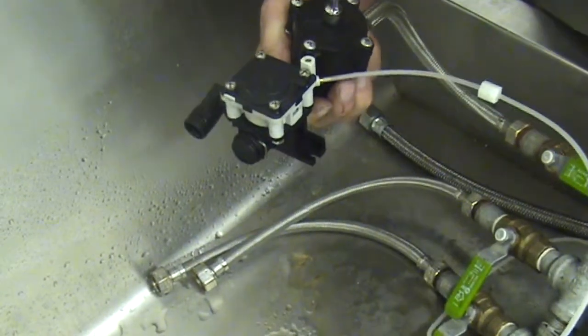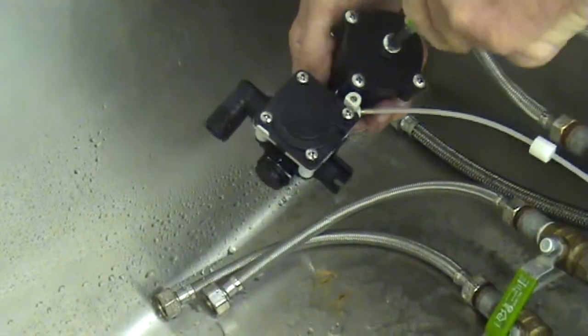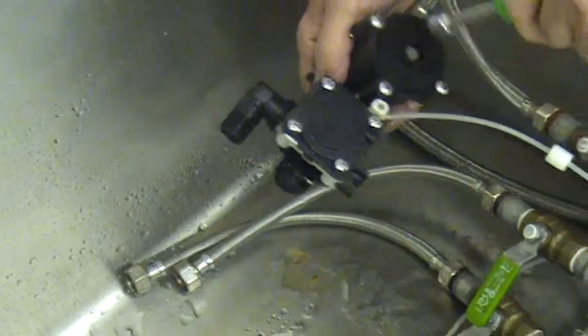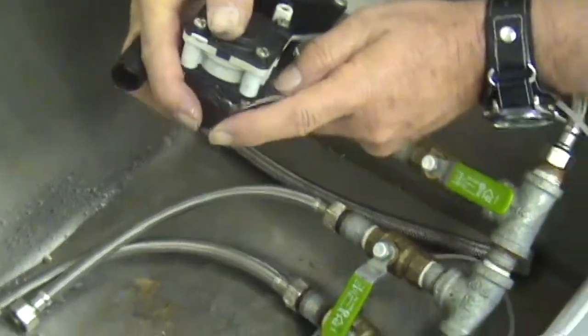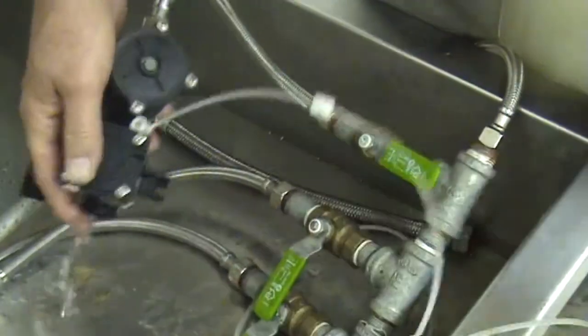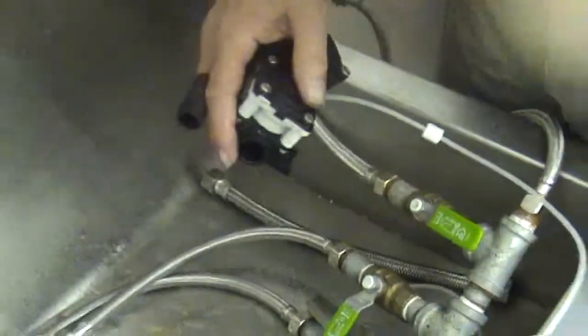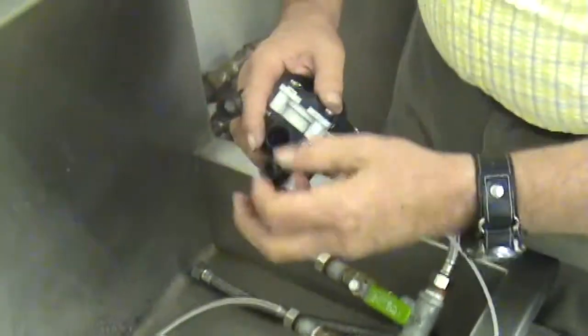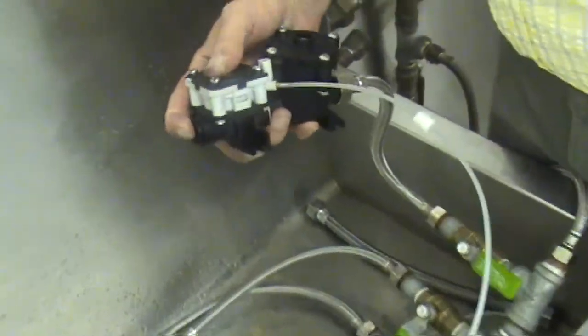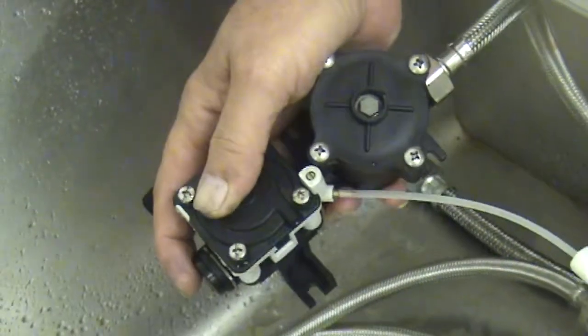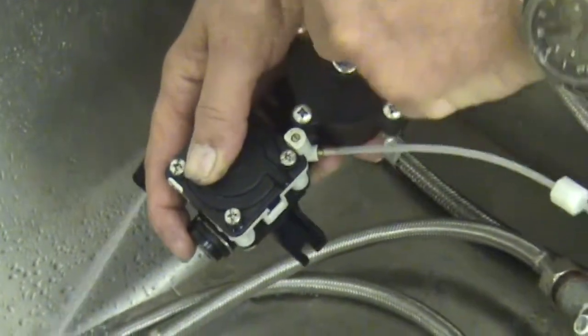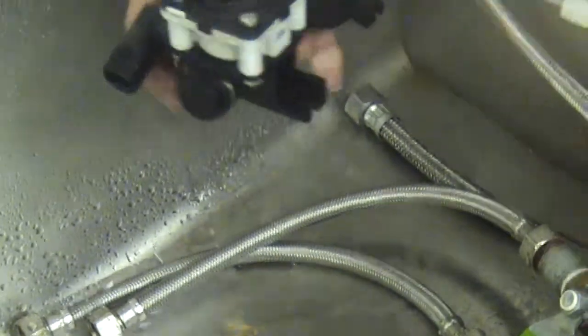Now, I would say that o-ring probably has some kind of defect in it that's keeping it from sealing. So it's best to replace that with another one. I'm just going to find another plug with an o-ring on it. See if we can't correct it that way. There we have it. It seems to be sealed this time.